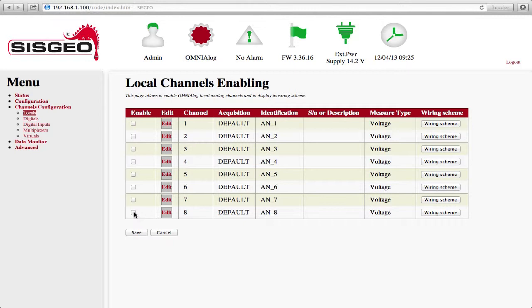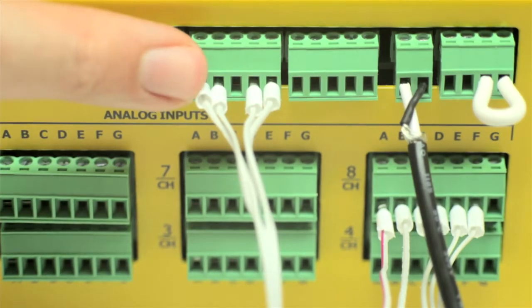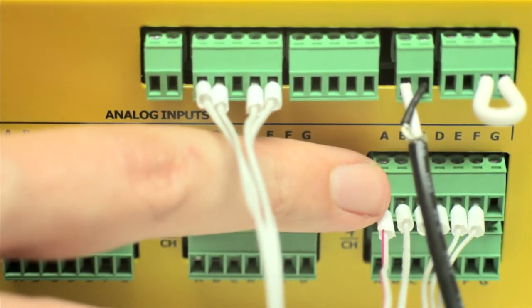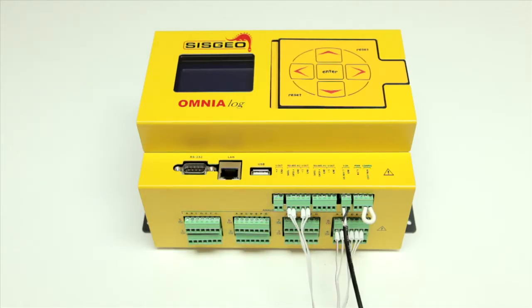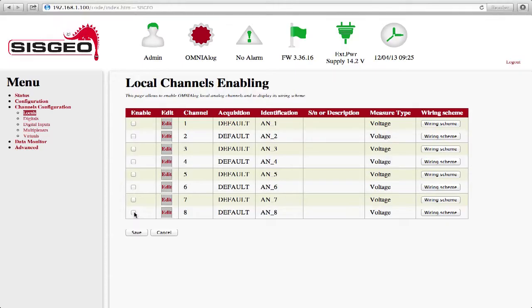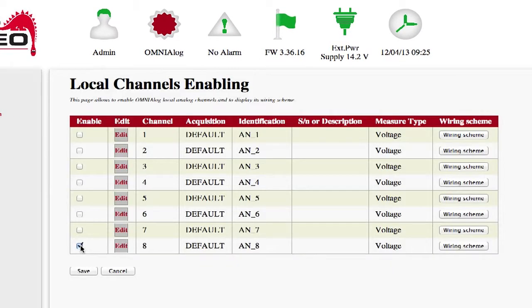To read the channels of multiplexers connected to Omnialog, it is necessary to enable the Local 8 Analog channel and configure it for multiplexer. The suitable connections between the Channel 8 terminal, the RS485 terminal and the multiplexer board will be made in the factory. Enable Channel 8 by ticking the Enable box and pressing Edit.